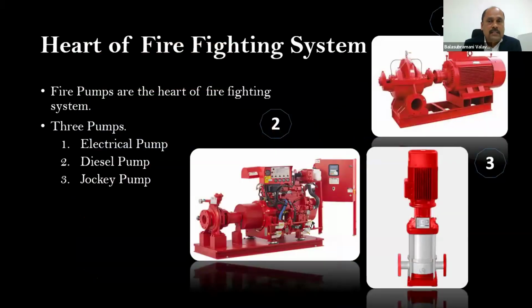And in the firefighting system, we have seen water is being utilized to extinguish the fire. Where is the water coming from? It is coming from the fire pump room. Hence fire pumps are called the heart of the firefighting system. In general, whatever we have seen in deluge or even the sprinkler part, there will be 3 pumps: the jockey pump, the electric pump, which is the running pump, and the third one is the standby pump, which is a diesel pump.